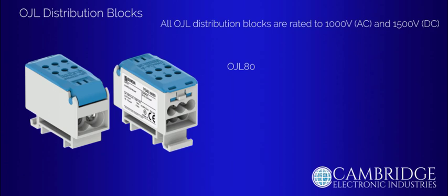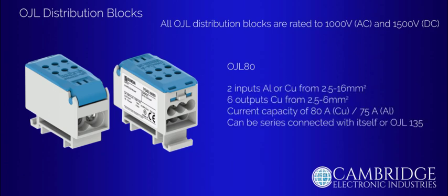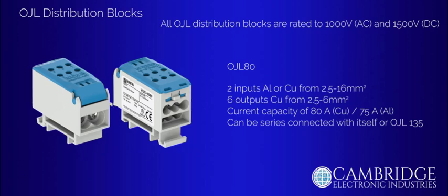OJL 80 distribution blocks offer 2 inputs and 6 output contacts and are capable of accepting up to 80 amps of current when using a copper cable or 75 amps for an aluminium cable on the input contacts. The OJL 80 blocks can be mounted on a DIN rail and are available in both transparent top covers or PA66 covers in black, grey, green and blue.